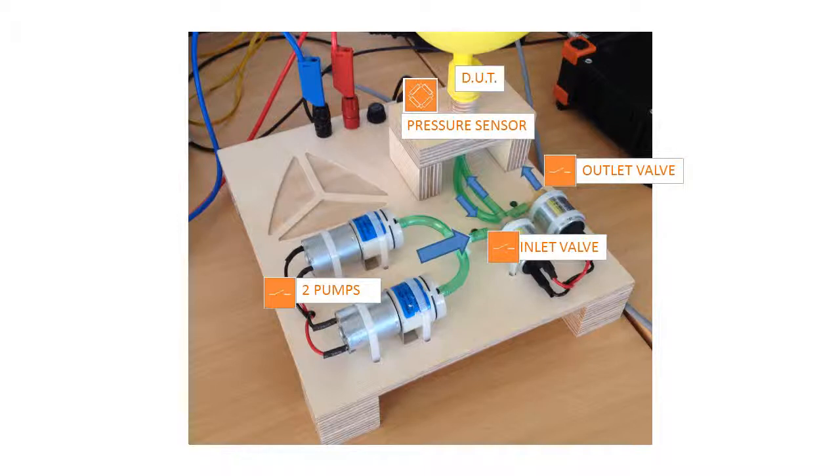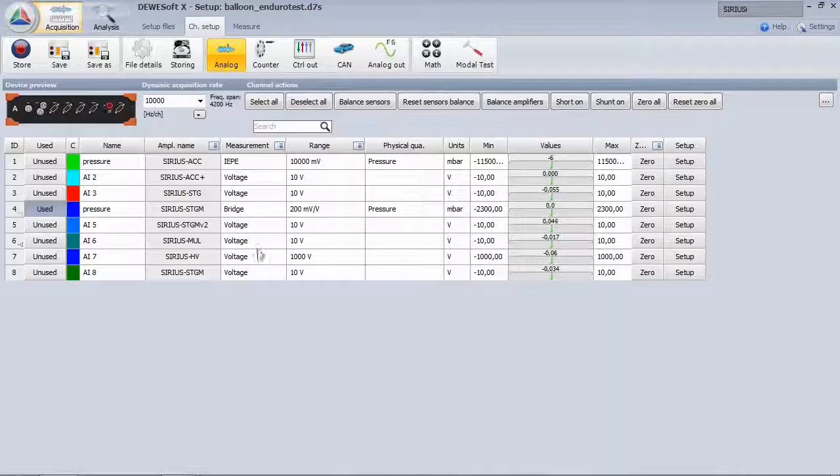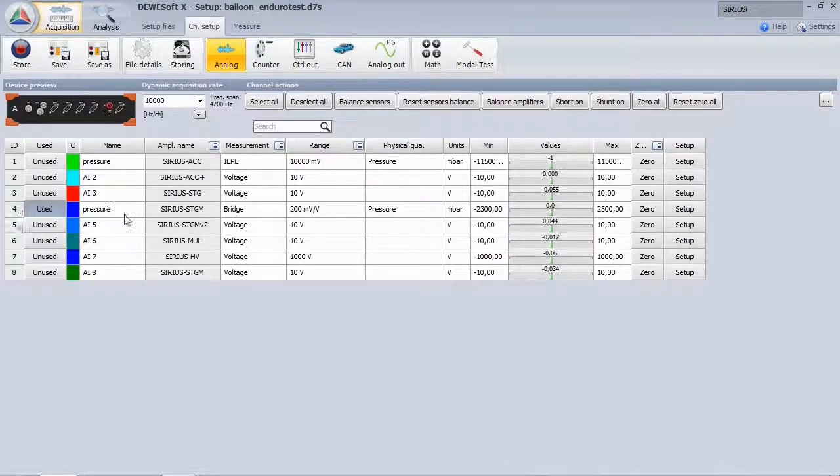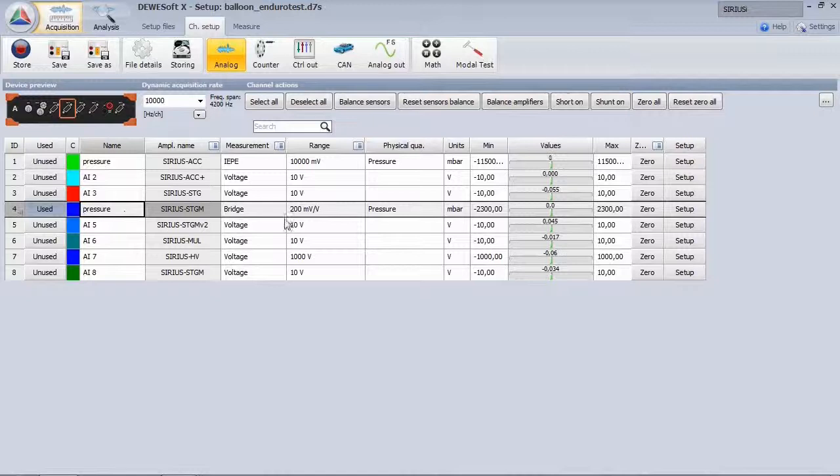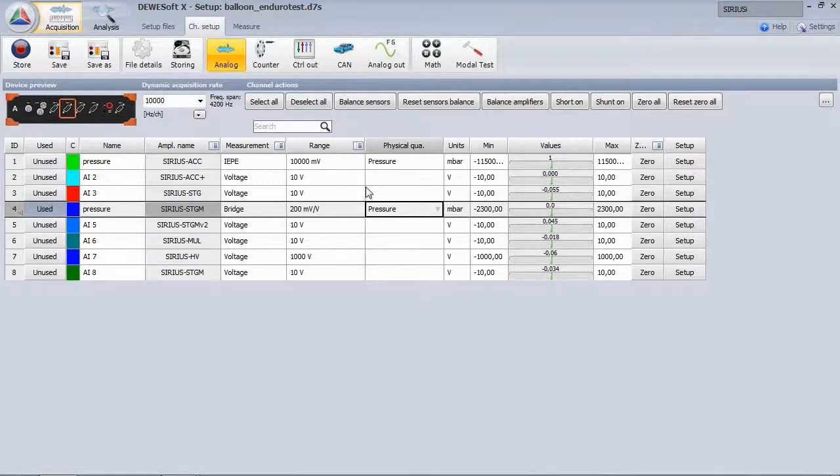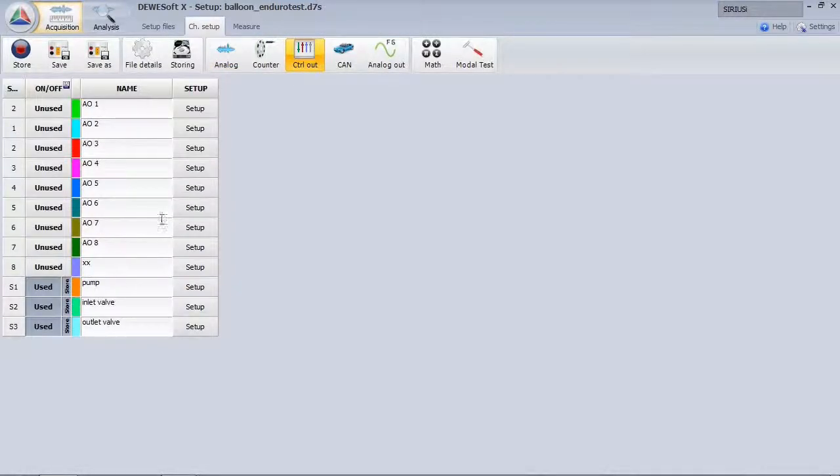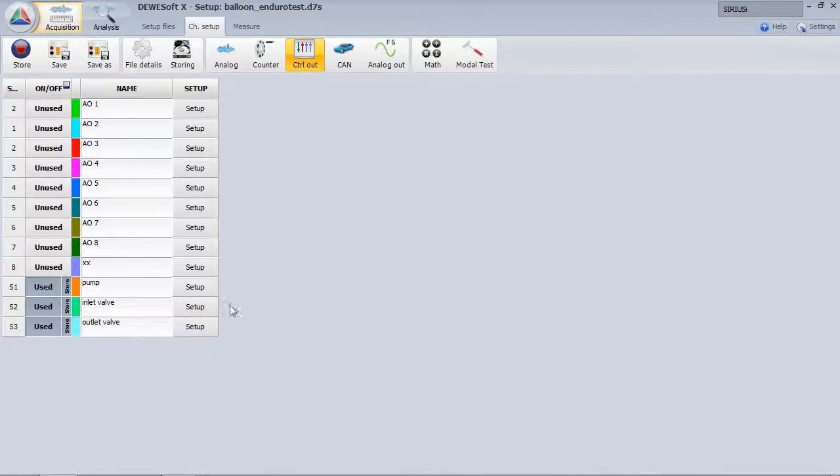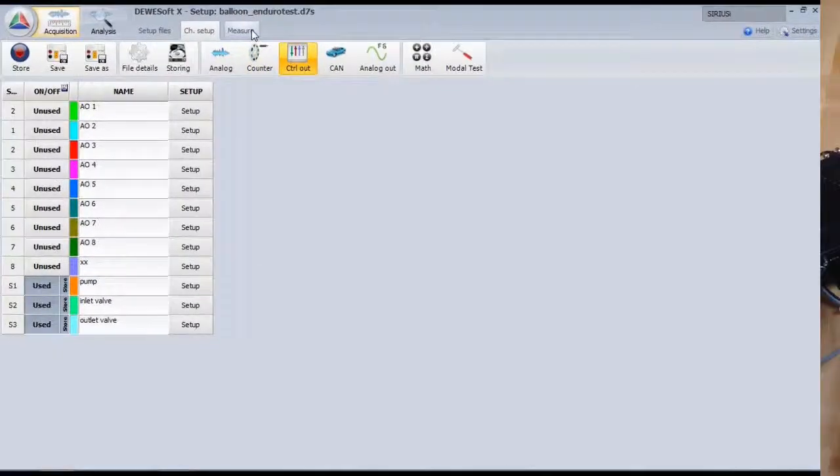Let's look at the DEWESoft setup. The pressure sensor is full bridge circuit and connected to a Sirius STGM module. The sync port was switched to digital out. Pump inlet and outlet valve can be accessed via control channels now.